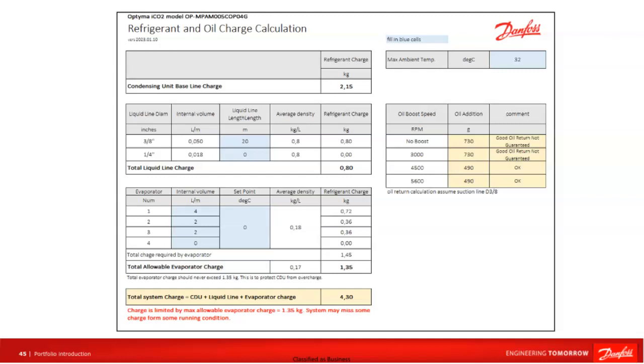It's worth paying attention to the area marked in blue, where we make the appropriate entries. First, we provide the maximum ambient temperature and then complete the information regarding the length of the pipeline, the volume of evaporators, and the evaporation temperature. This sheet will help us calculate the maximum refrigerant charge of the system and the amount of oil that should be added to the system to maintain its efficiency and reliability.